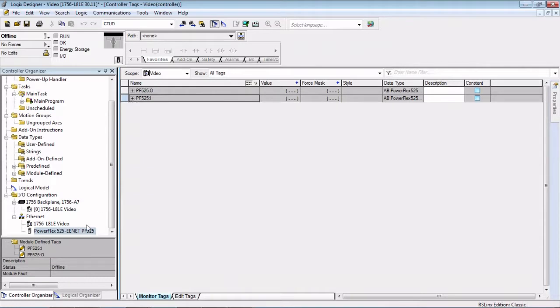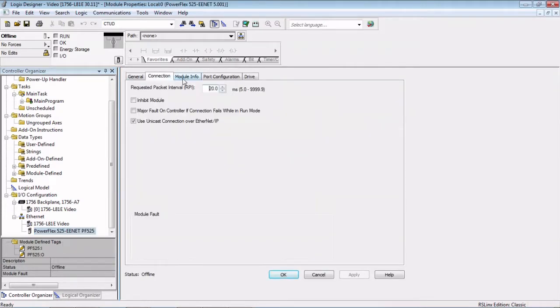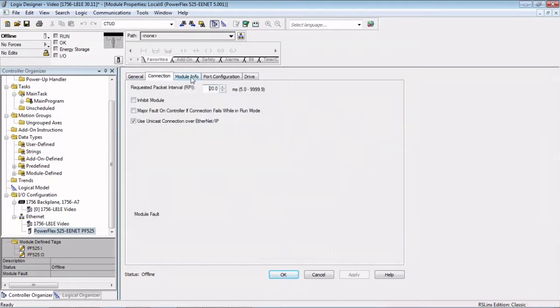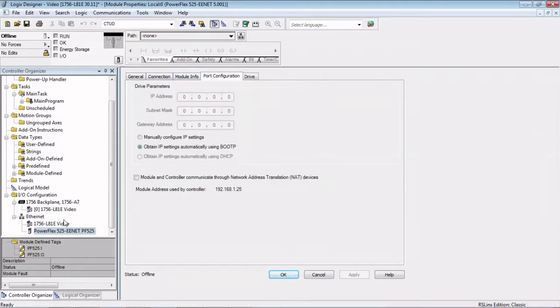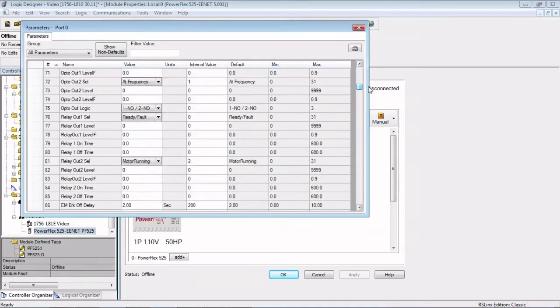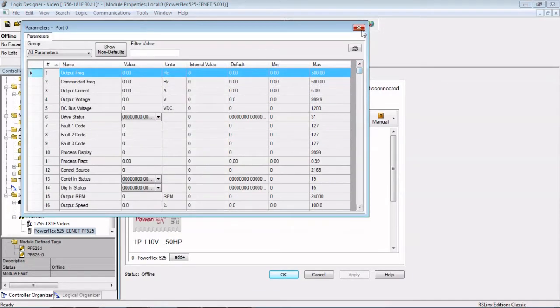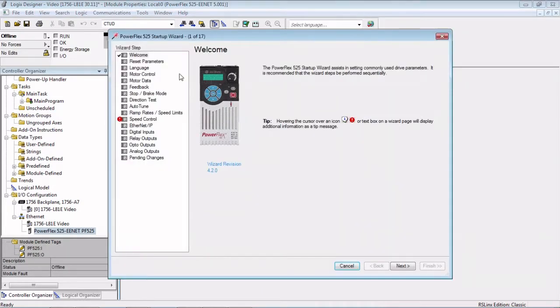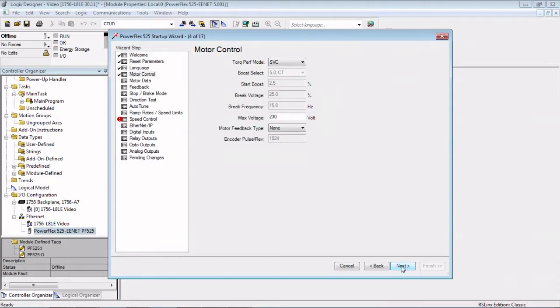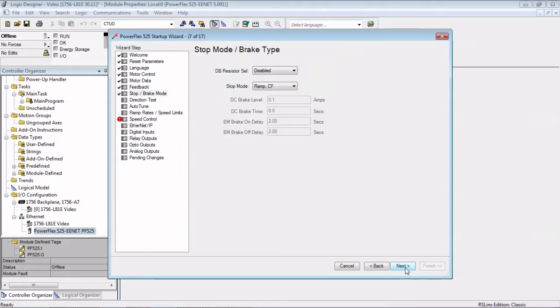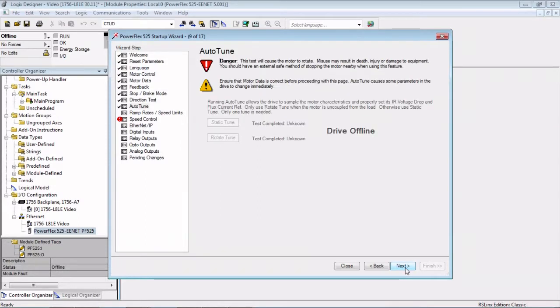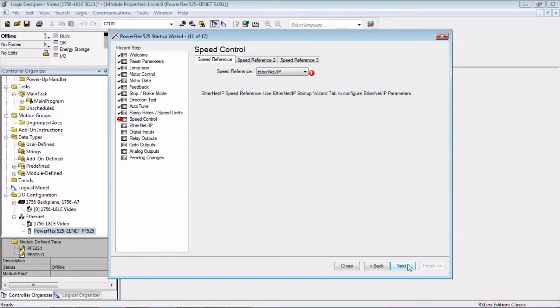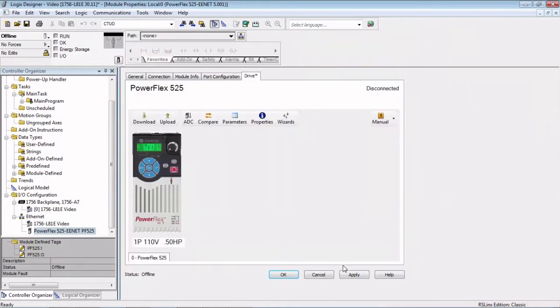It's just that easy. Something else you can do with the add-on profile for a drive. As well as having the connection, the RPI, the port configuration that you would have for any other I.O. card or remote I.O. drop on the network, you also have this drive tab. Here we can actually connect to the drive, program its parameters, and there are startup wizards. The startup wizards will step you through the initial configuration of the drive. You put in what type of control, your nameplate data, and this is all stuff that you could do from the HIM before, but now you don't need to walk out to the drive. You can do it right from Logix. And then you can save that.